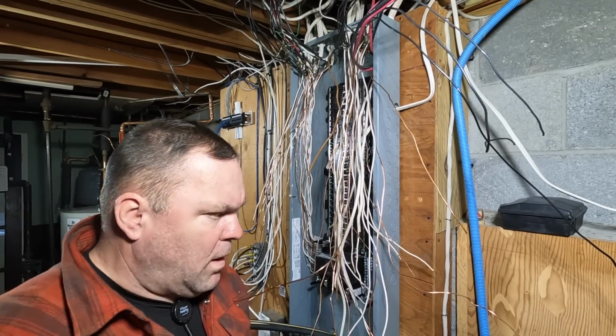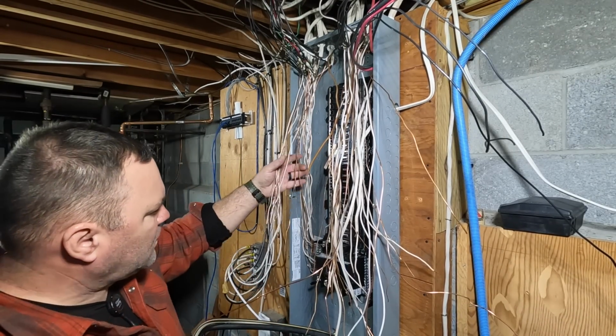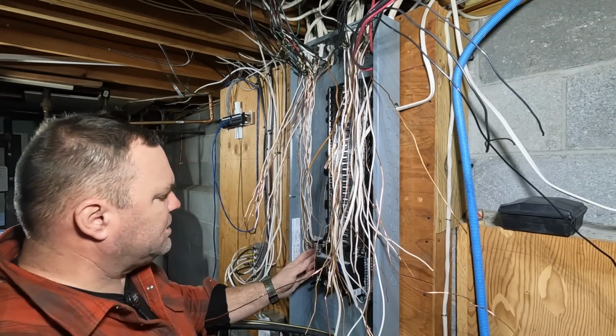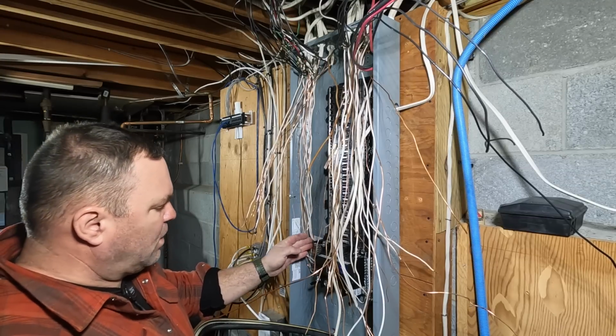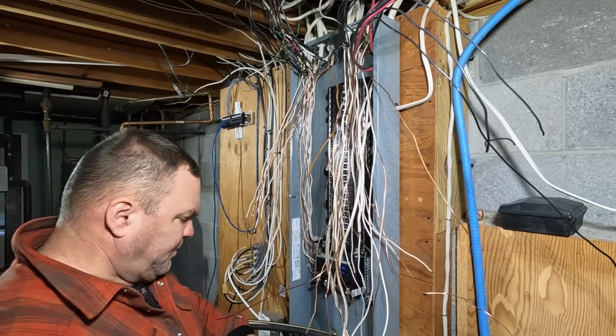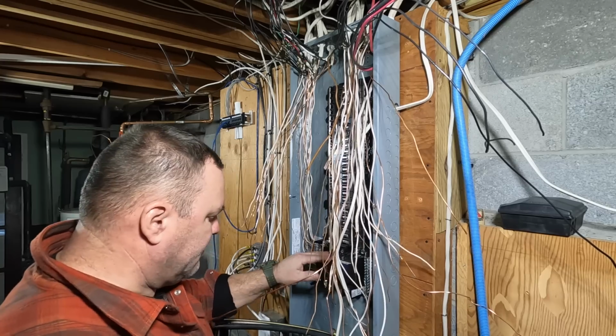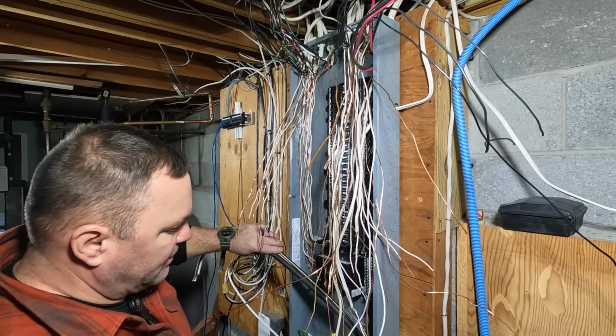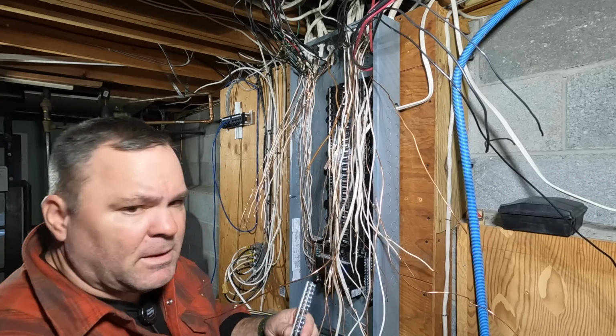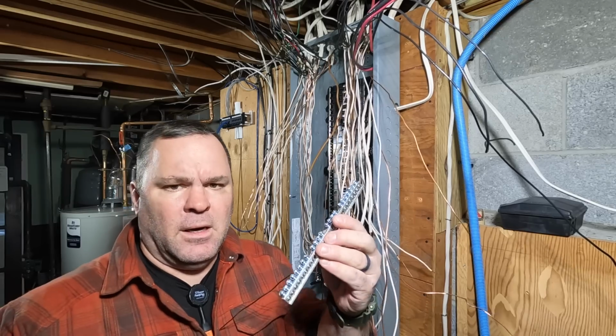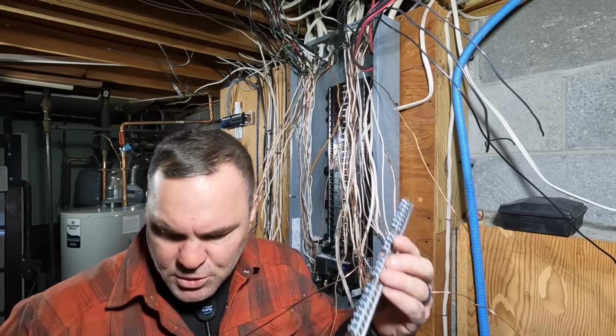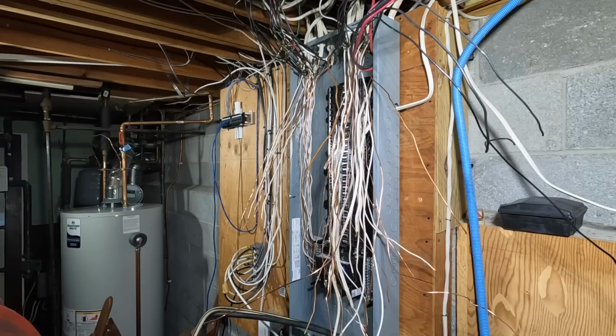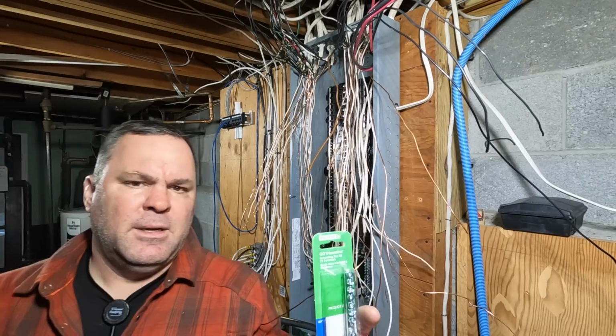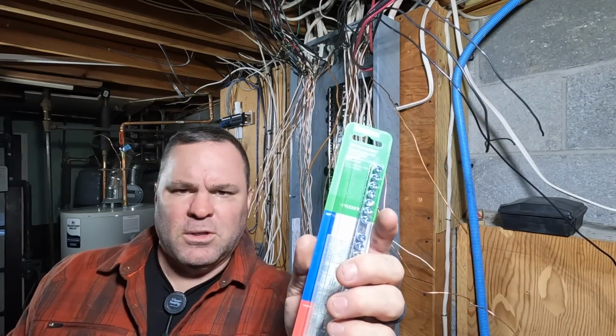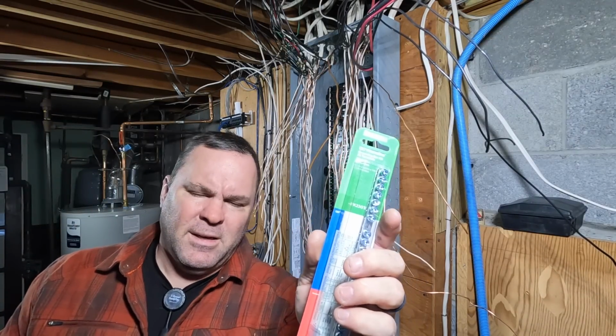All right, so I ran into a little issue where the rest of these grounds and neutrals are not going to reach the bus bar for the neutrals and grounds that came with the panel. Because I had to put the disconnect at the bottom, because of the length of my service entrance conductors, I'm going to add a ground bar to the enclosure. And as you'll see, I got 2 of them. It's made by Square D for QO or the Homeline line of panels.